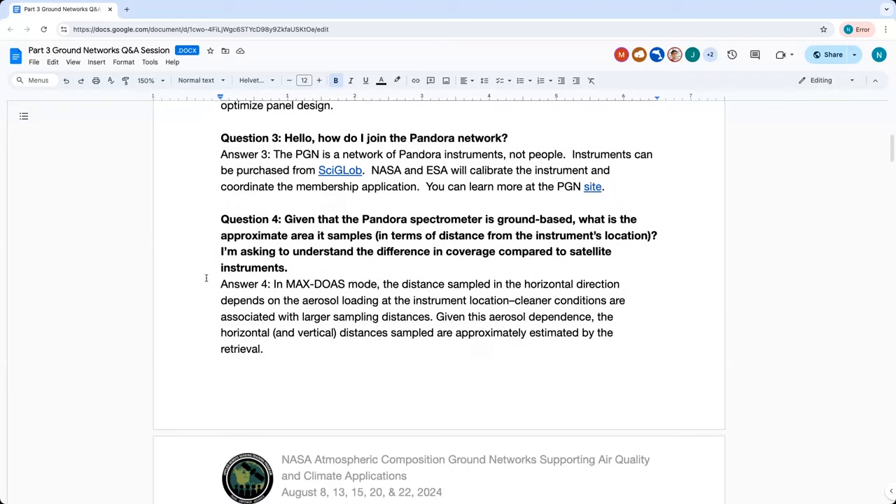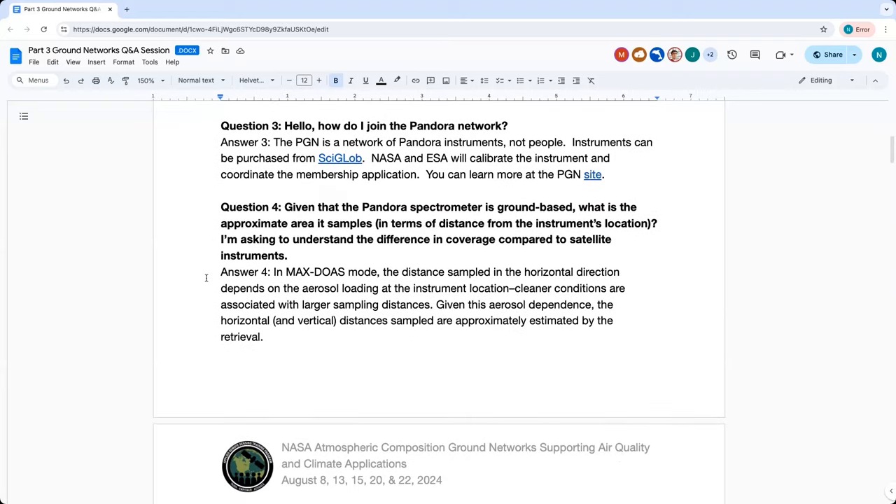Question three: How do I join the Pandora network? The network is a network of instruments, not people — instruments join the network. Instruments can be purchased from SciGlob, and then you're given an option of joining the network. Some people buy instruments and never join the network because they have their own research goals. But once you buy an instrument, NASA and ESA will calibrate the instrument and coordinate the membership application.